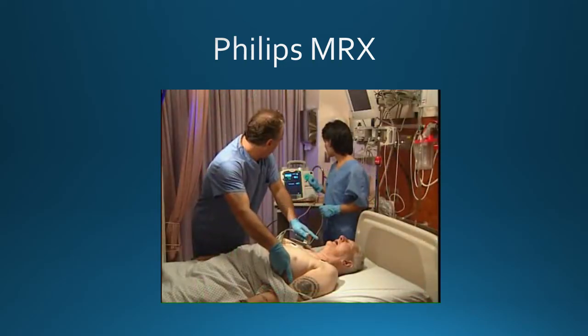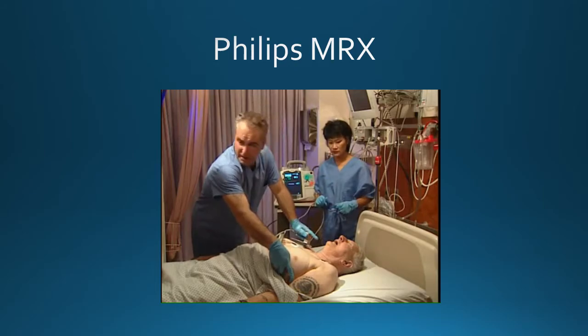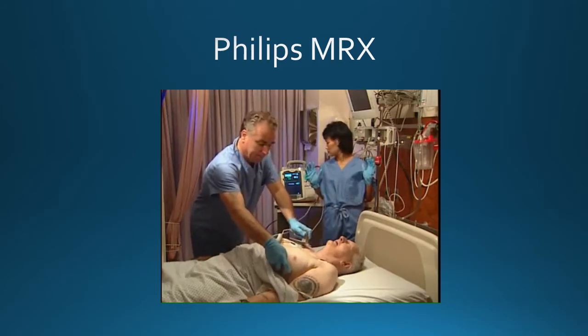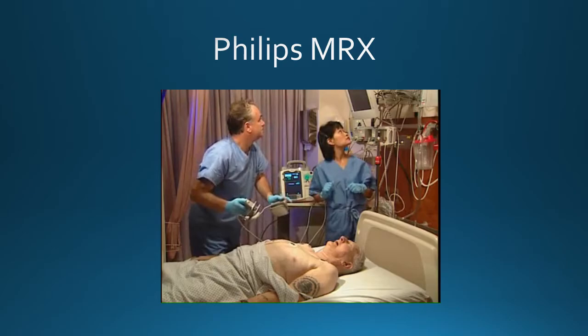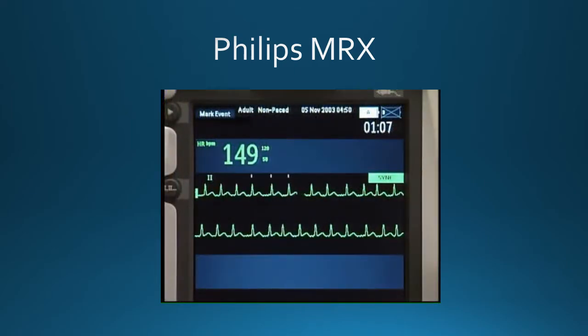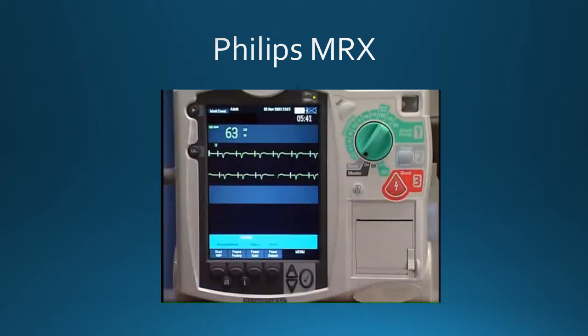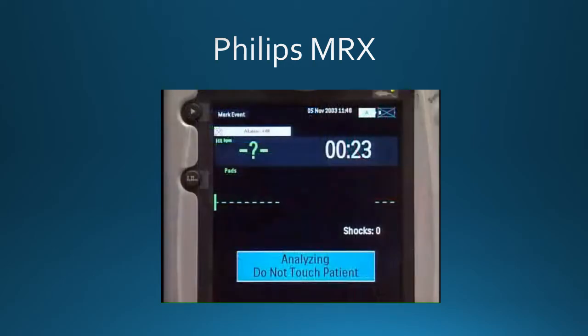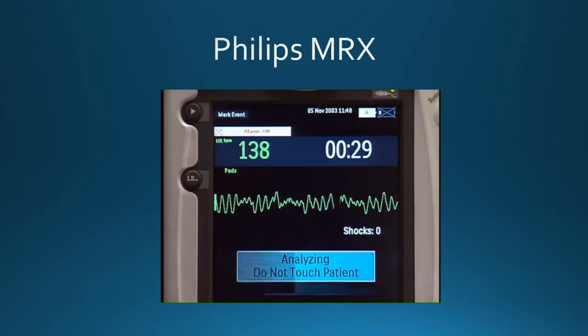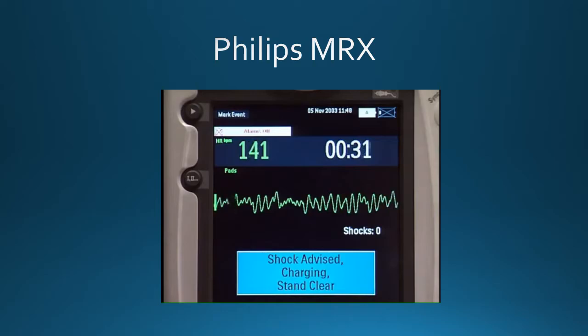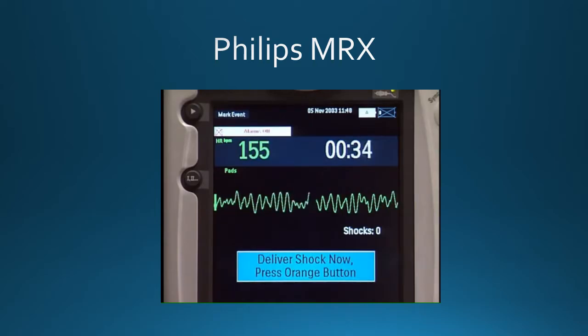Manual defib mode offers simple 3-step defibrillation using paddles or multifunction electrode pads. Manual mode also allows you to perform synchronized cardioversion. The optional pacing mode offers non-invasive pacing therapy. In AED mode, the HeartStart MRX analyzes an 8-year-old to adult patient's ECG, determines whether a shock is advised, and guides you through the defibrillation process.